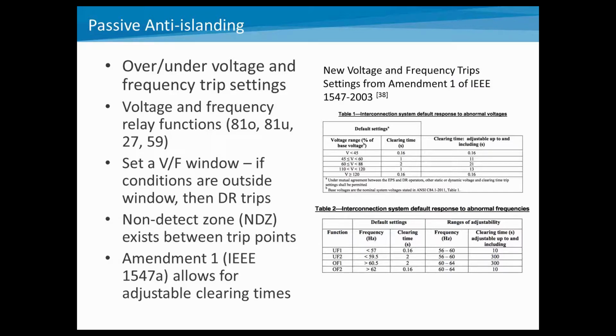Now, when you use a passive anti-islanding technique, there is basically what they call a non-detect zone if your voltage and frequency is being maintained within those areas. And so if you are able to create a stable island condition, but your voltage and frequency don't go outside the normal operational areas, passive anti-islanding can be fooled. That being said, it's very difficult to maintain that matched real and reactive power setting with your distributed generation in there.